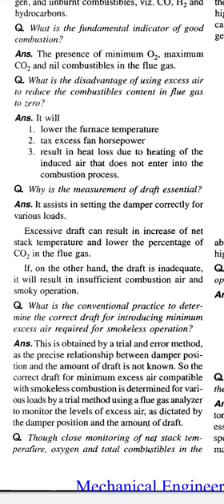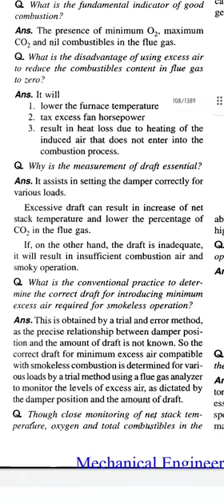Question. What is the conventional practice to determine the correct draft for introducing minimum excess air requirement for smokeless operation? Answer. This is obtained by trial and error method as the relationship between damper position and the amount of draft is not known. So the correct draft for minimum excess air compatible with smokeless combustion is determined for various loads by a trial method using a flue gas analyzer to monitor the level of excess air as dictated by the damper position and amount of draft.